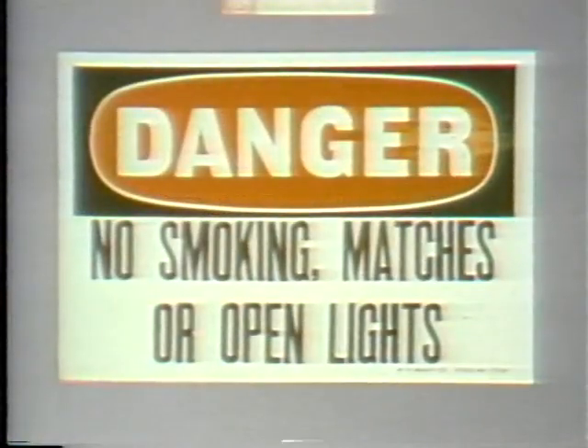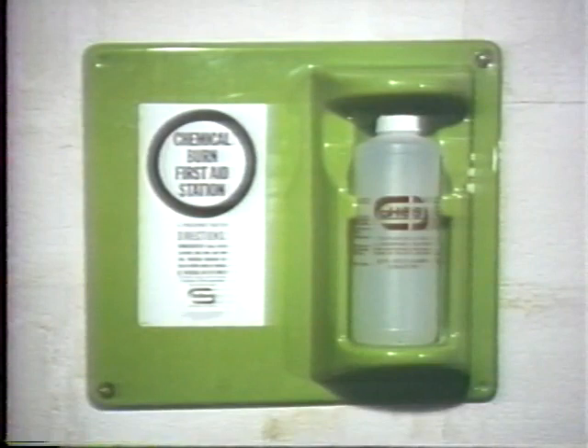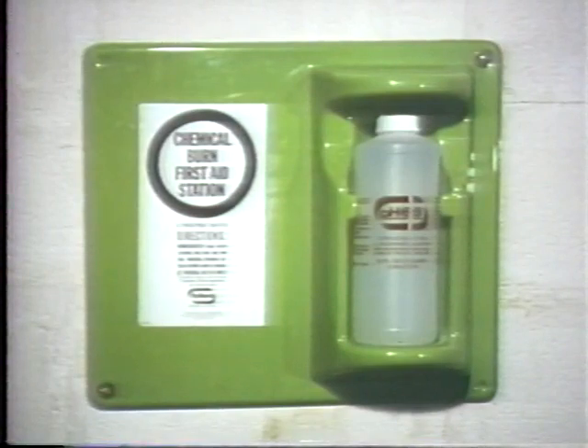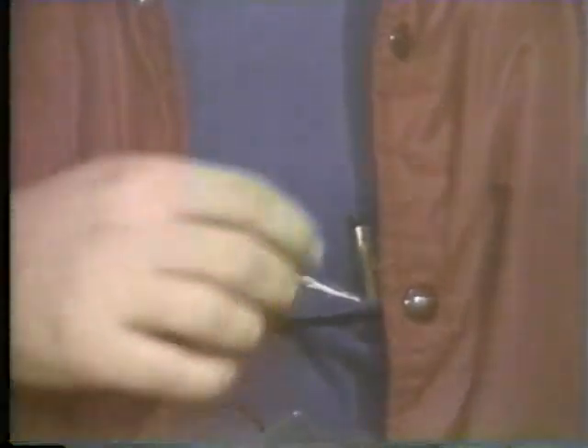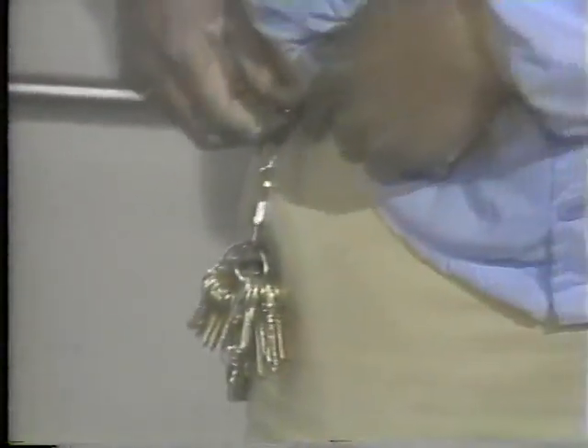First of all, no smoking and no open flames. Batteries give off hydrogen gas, which can be flammable and even explosive when mixed with air. Second, locate the nearest eyewash station — if battery acid gets in your eyes, you don't have time to fumble around. Third, don't carry any metal tools or equipment long enough to short across a pair of battery terminals. Remove any metal jewelry and other exposed metal on your body. Even if voltages are low, batteries can put out enough current to weld rings to fingers or give you severe burns.